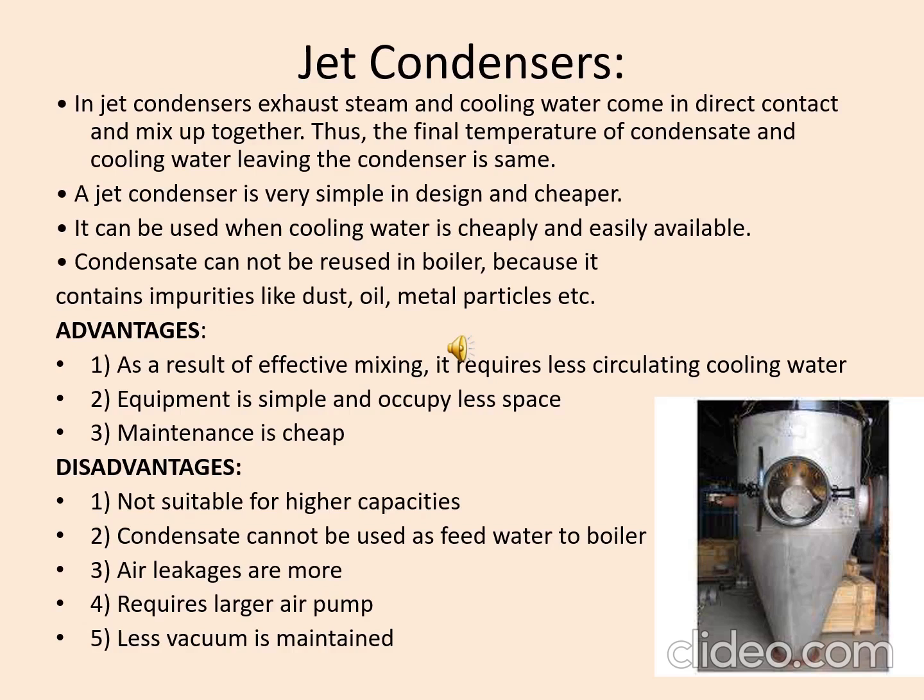Then disadvantage, it is not suitable for high capacity. Then condensate cannot be used as feed water to the boiler, because though it is direct contact with each other, some impurities like dust, oil, metal particles will be there. That's why it is not directly sent to the boiler. Okay, then air leakage is more, it requires a larger air pump. Then less vacuum is maintained here.